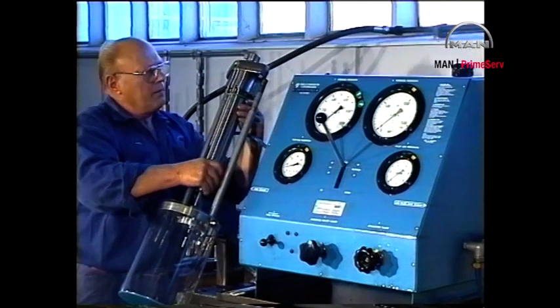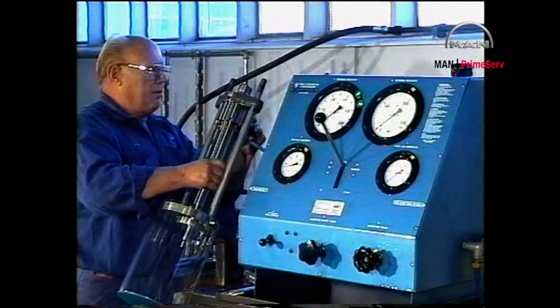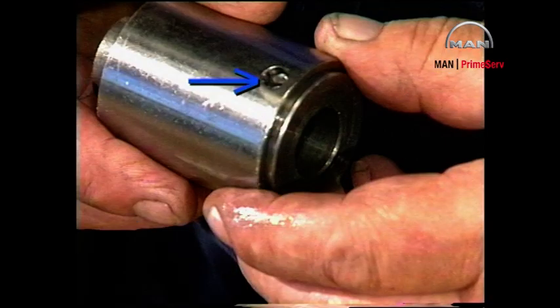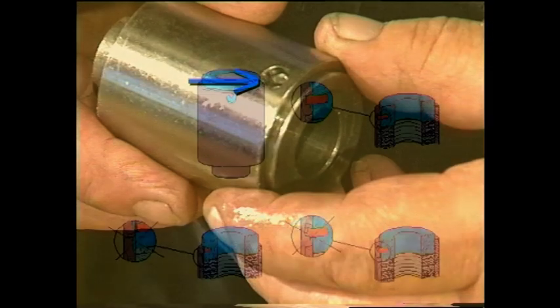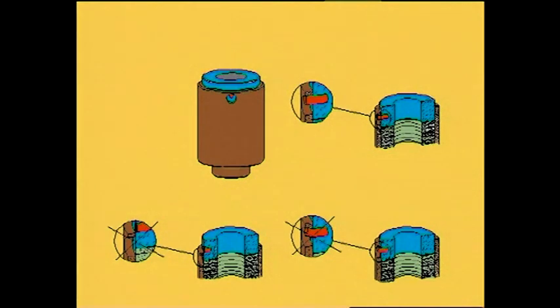Position the fuel valve in the test rig. For guidance on how to operate the pressure testing pump, refer to the supplier's special instructions. To ensure that overtightening has not taken place, check that the locking and indicating pins have not been bent or broken off. In the event of overtightening, mount a new spring housing.